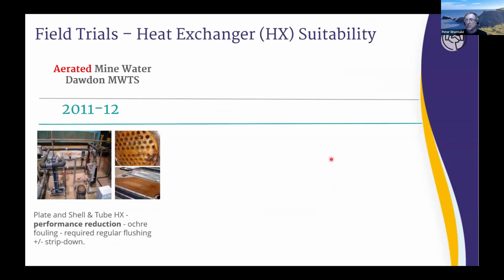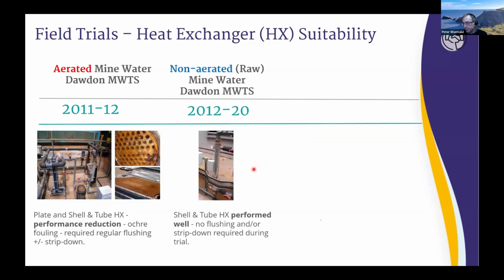So a few comments about some heat exchanger field trials which underpin the waste mine water heat program. Something over 15 years ago, we started experimenting with plate and shell and tube heat exchangers at our Dawdon mine water treatment scheme. There was a performance reduction because they were placed on the aerated side of the treatment process and with ochre fouling, you can see on the right, that required regular flushing and strip down. So the shell and tube heat exchanger was moved to the non-aerated or raw side of the treatment process. That performed well over the 8 years of the trial with no flushing or strip down required.